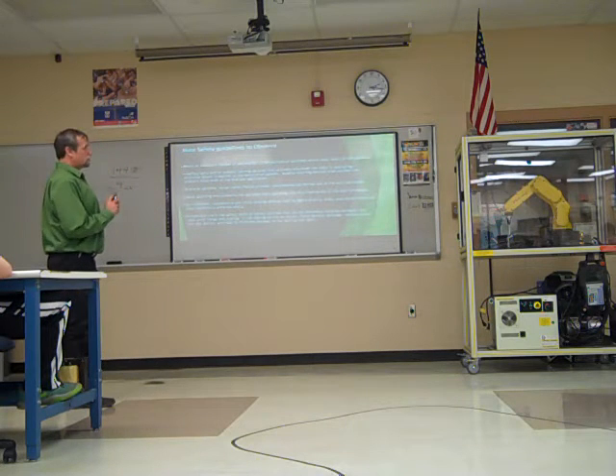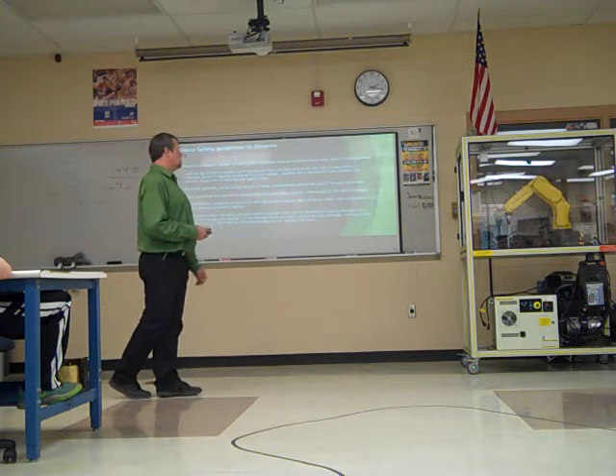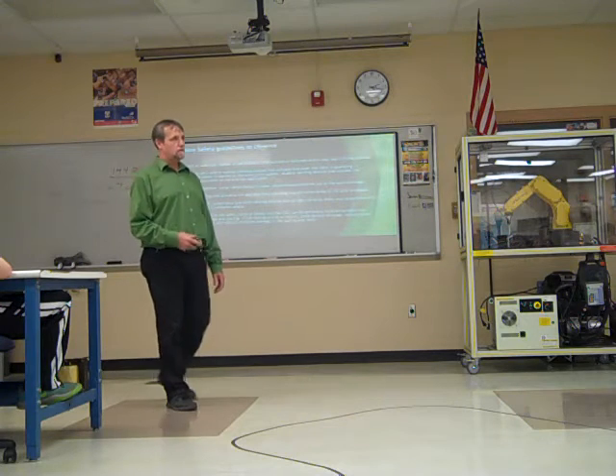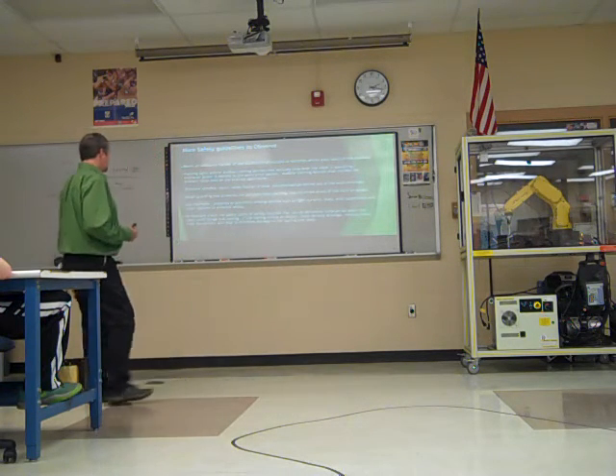Use interlocks, we already talked about that. Proximity sensing devices, light curtains, mats, different systems that know where somebody's at. So if somebody gets in the wrong place, the robot will shut down.